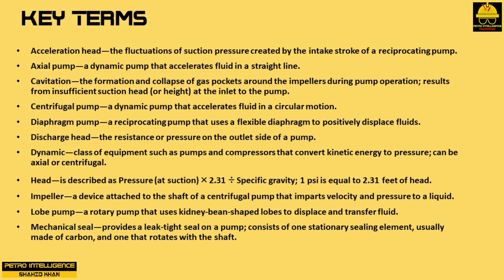Acceleration head is the fluctuations of suction pressure created by the intake stroke of a reciprocating pump. Axial pump is a dynamic pump that accelerates fluid in a straight line. Cavitation is the formation and collapse of gas pockets around the impellers during pump operation, which results from insufficient suction head, or height, at the inlet to the pump. Centrifugal pump is a dynamic pump that accelerates fluid in a circular motion.